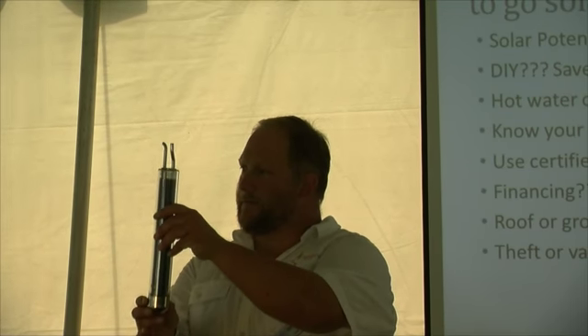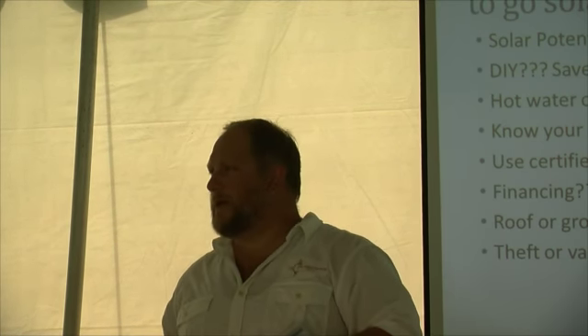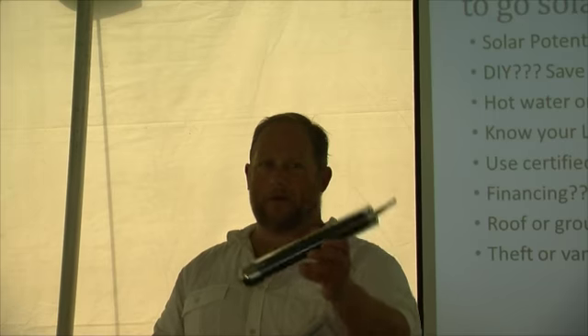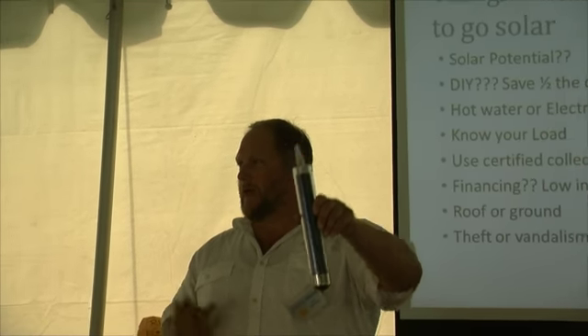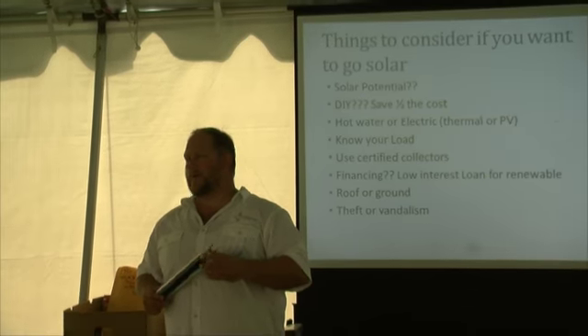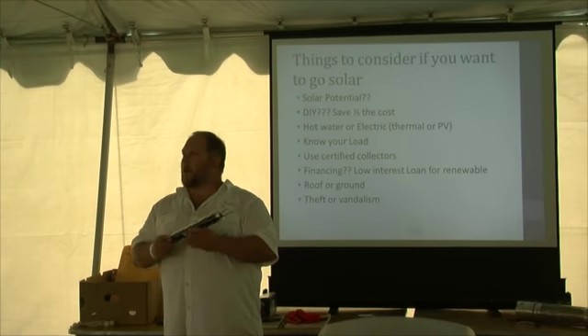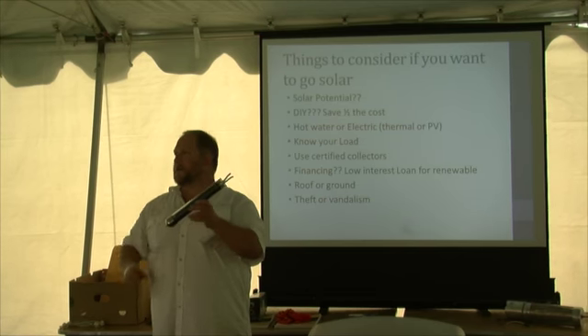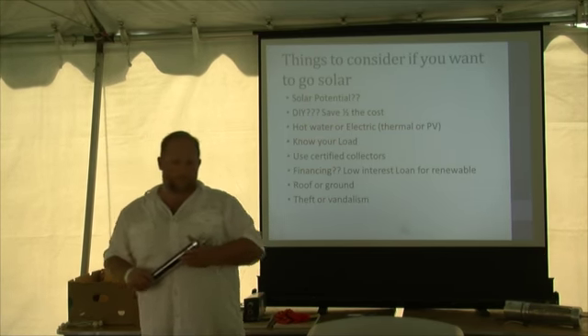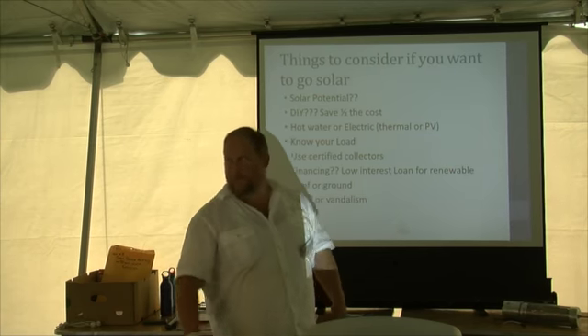What about flat plates? It depends on the manufacturer. A lot of them have ventilation issues, so if you don't allow moist air to move through the collector, you'll get condensation. Some manufacturers design specifically for flat or flush mount, so you have to check with each one, but most require a certain pitch to allow for ventilation inside the collector. That's going to be manufacturer specific.